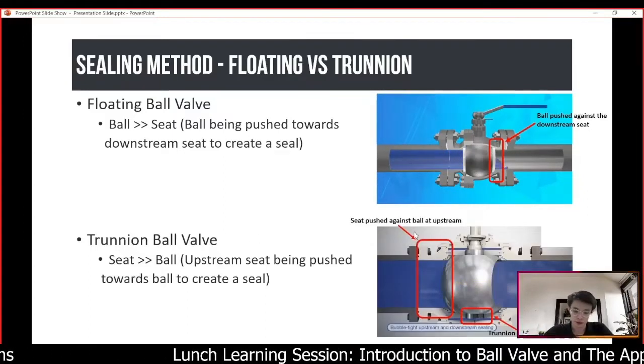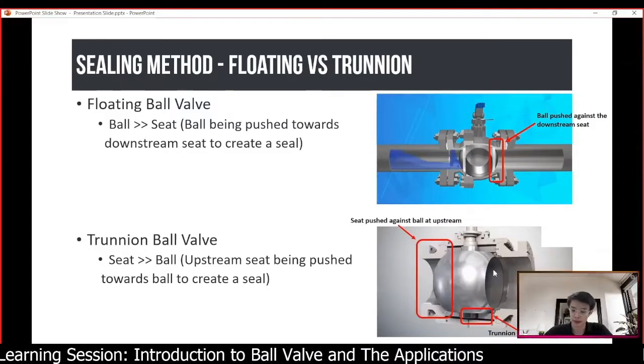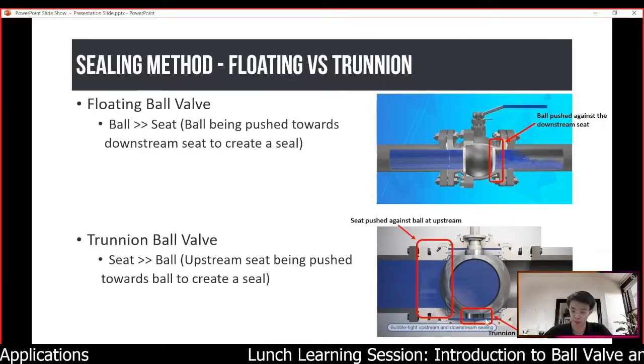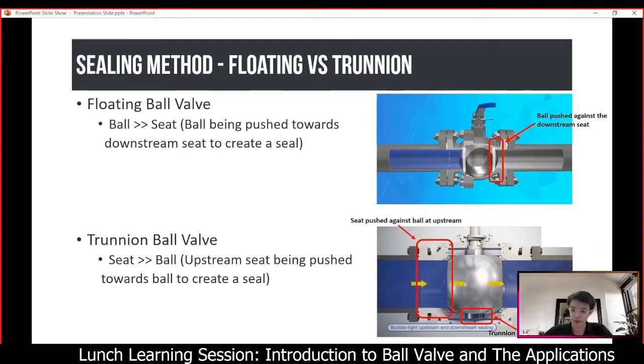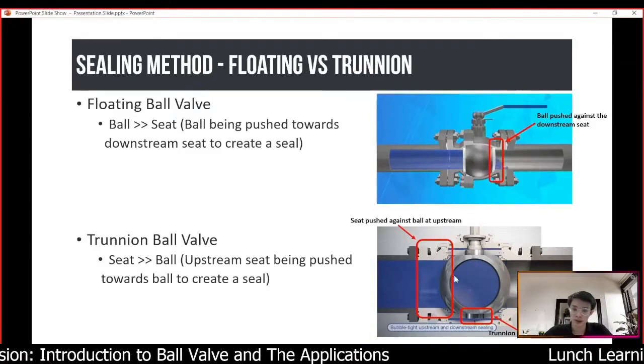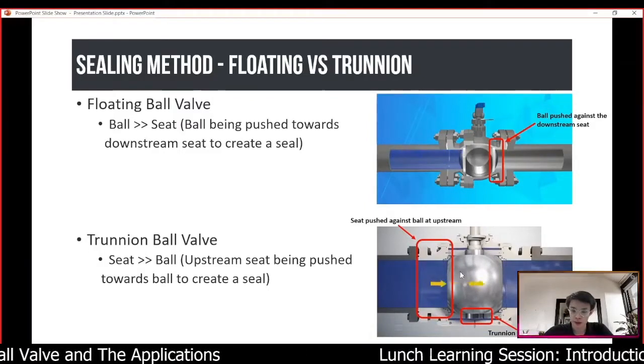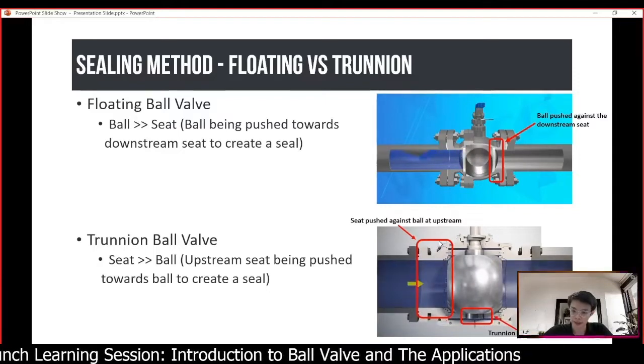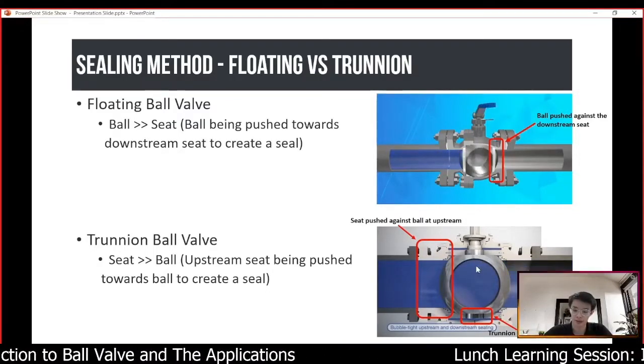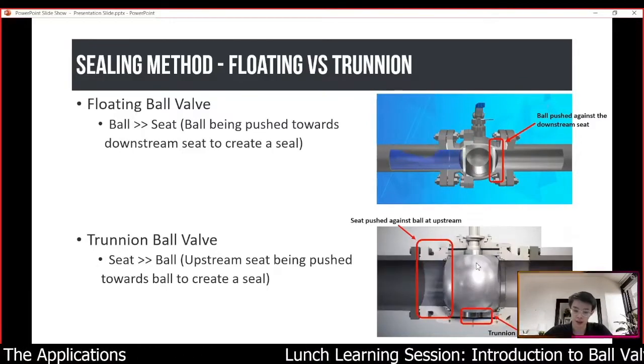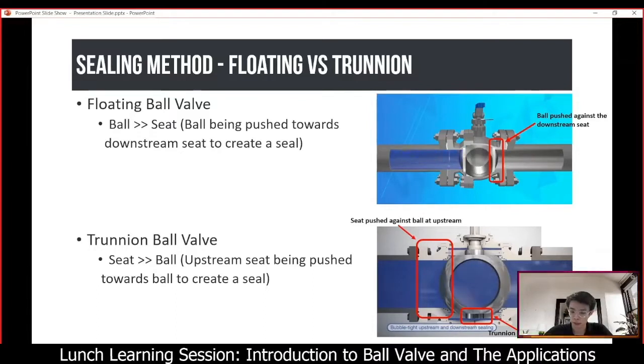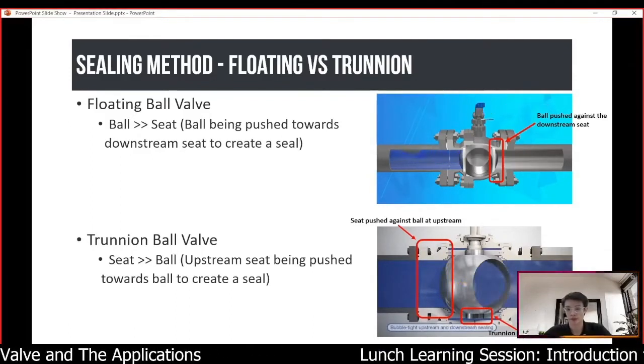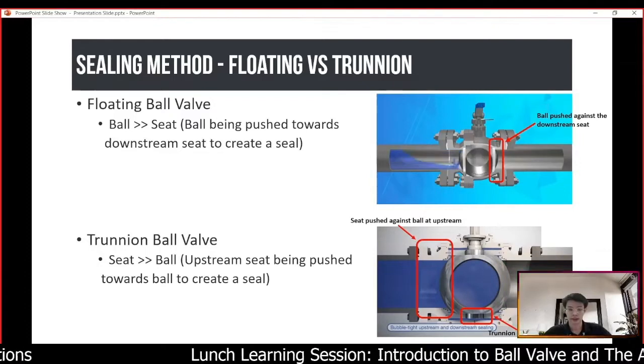For the trunnion ball, the ball rotates in a fixed position because there is a fixed support at the top (the stem) and also at the bottom (the trunnion). When pressure comes from upstream it pushes the seat against the ball to create a seal. The trunnion ball is suitable for large size and high pressure applications because the ball will not deform the seat as easily as a floating ball.